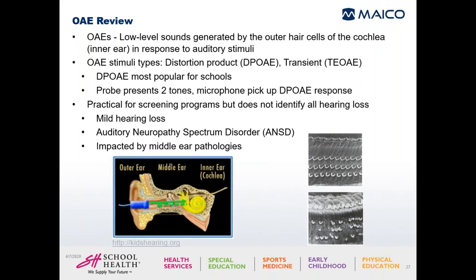Even though it is a practical screening method for a variety of ages, with newborns all the way up through adults able to have this test done, there are some disadvantages. It doesn't detect mild hearing losses or auditory neuropathy spectrum disorders. Any hearing loss that is after the cochlea would not be detected with this particular device. And as I said, it's very impacted by middle ear pathology. If you have an infection or something in that middle ear space, it is going to be very difficult for the sound to go through that space, and even more so to come back out to be picked up by that probe.